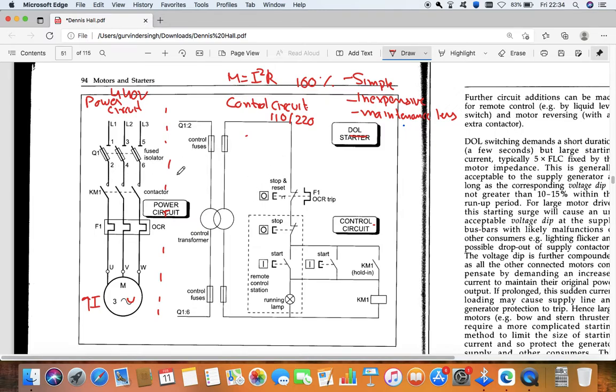Now I will explain how this control circuit works, but before that I will explain a few of its components. The main component in the power circuit is the motor that is going to run, then the OCR relay, that is the overcurrent relay. If the motor is drawing more current, this relay will open and stop the motor. Then we have a contactor, these three contacts, which must make before the motor will run. Then fuse isolators: if there is a short circuit, the fuse will burn out. In the control circuit we have a transformer, a stop switch, a start switch, a contactor, a relay, lamps and fuses. I hope you all know what a control transformer is. It is just a step down transformer.